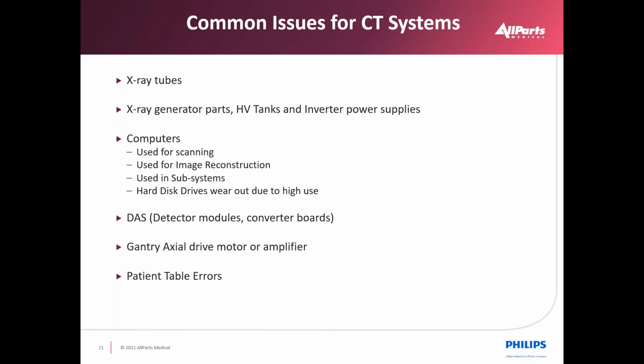Then we have the detector modules themselves. Crystals are part of the detector module. We talked about that earlier, where the X-ray is converted by the crystal into a light, whether it's a visible light or an infrared light, and the photodiode picks that up and then converts it using the converter boards to A to D, our digital values that we then transmit to the recon computer hardware. Crystals and radiation are not friends. Crystals will degrade as exposed to radiation. So over time, a detector module will degrade and then at some point fail in its life. And then those can be replaced as well.